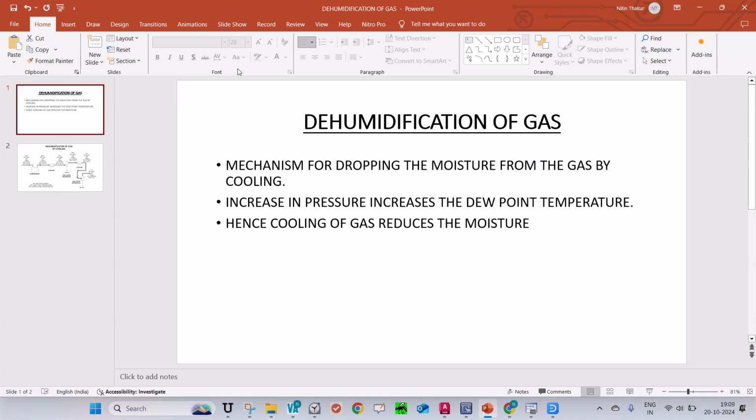In broad terms, a few examples that come to my mind right away are biogas that we have to dehumidify before we send it to the VPSA, PSA, or even the membrane system. There is a limit for the VPSA that there should be no free moisture. And the less moisture is better, because then the media will be used for removal of carbon dioxide instead of removal of moisture, so it will have a longer run time.